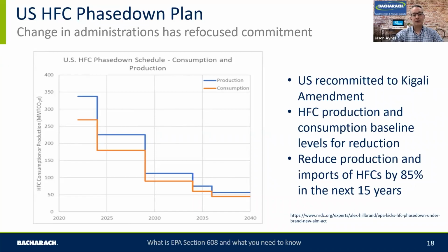After 2 years, there is a significant step down, around 20 to 30%, that's going to be available on the market. So that will start to create potential supply and demand issues, or start to guide people to look at low GWP refrigerants. And you can see this step down. There are two significant step downs in the early stages, in the first 8 to 10 years, and then it levels out at the bottom. Why is the US doing this? Part of the Kigali Agreement and the US committing to that now is to reduce CO2 in the atmosphere and obviously temperature rise. So the American and US system is aligning, becoming a leader in reduction of GWP refrigerants on the marketplace. And again, it's targeting those HFC refrigerants, and it's about supply, demand, and consumption.